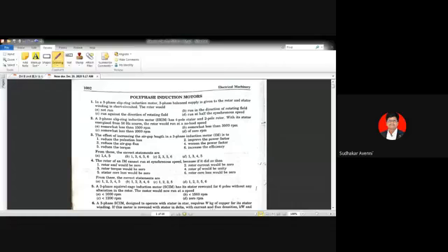So see here, in a squirrel cage induction motor, the rotor poles are developed based on mutual induction. But a slip ring induction motor is not like that. When we design the stator as 4 pole, definitely we design the rotor also as a 4 pole rotor. If we design the stator as 8 pole, the rotor is also designed with 8 pole. There is no mutual induction between the pole forming of the rotor in the case of a slip ring induction motor.